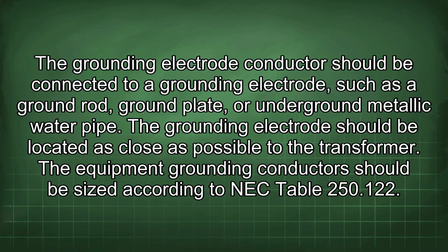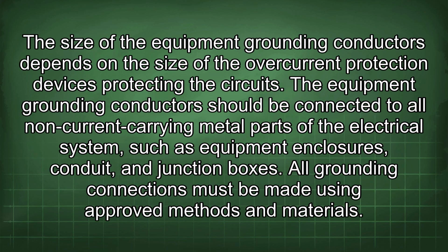The grounding electrode conductor should be connected to a grounding electrode, such as a ground rod, ground plate, or underground metallic water pipe. The grounding electrode should be located as close as possible to the transformer. The equipment grounding conductor should be sized according to NEC Table 250.122. The size of the equipment grounding conductors depends on the size of the overcurrent protection devices protecting the circuits. The equipment grounding conductors should be connected to all non-current carrying metal parts of the electrical system, such as equipment enclosures, conduit, and junction boxes.